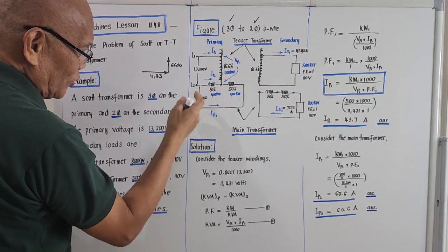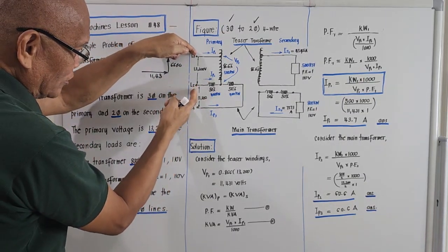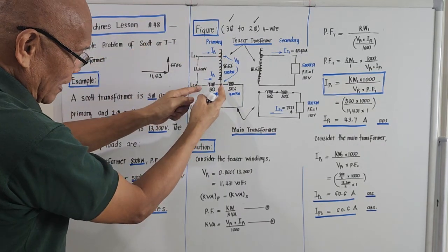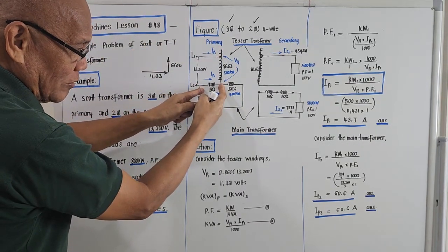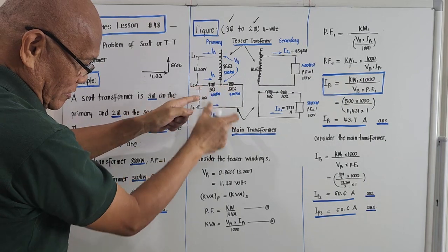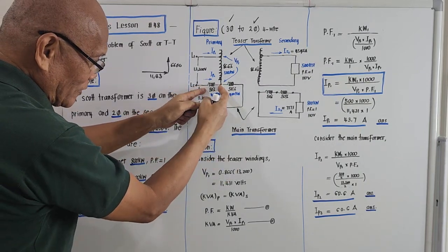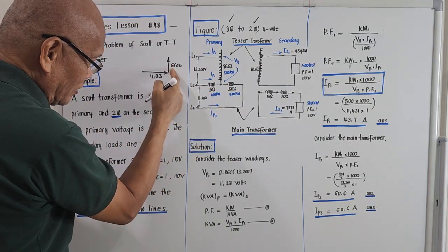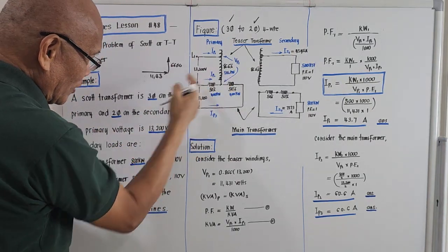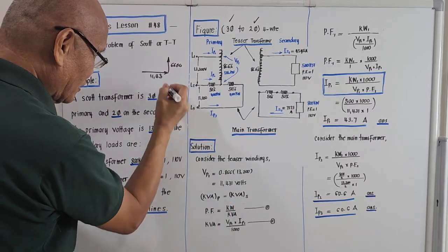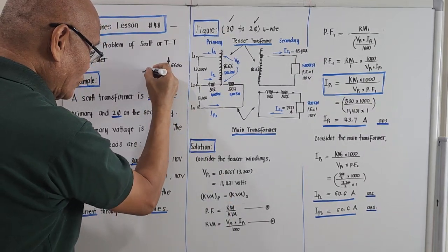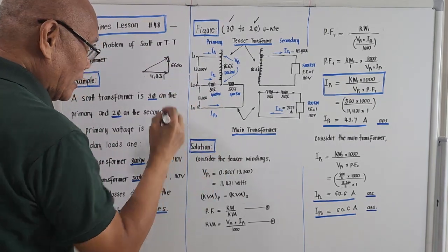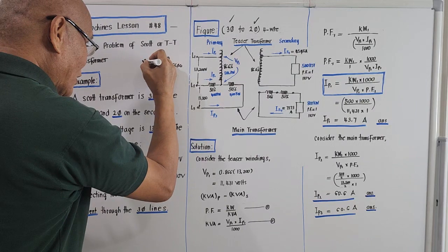If we measure the voltage across this, it should be the voltage across the 86.6% tapping plus the 50% on the main transformer tapping, meaning 50% of the line to line, so that's 6,600. The 86.6% is 11,431. If we take the vector sum of these, adding vectorially, it should be equal to 13,200 volts.